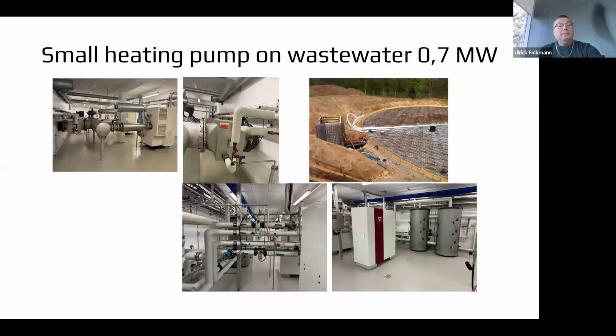Next slide, please. And what we did at this plant was we put in a lot of small hoses around the bottom of the tank, and we put concrete on top of it, and then we added around 20 feet of water in the tank. So here we have a 100% stable temperature of 57 Fahrenheit the whole year round. And we cannot see anything that does something to the bacteria.